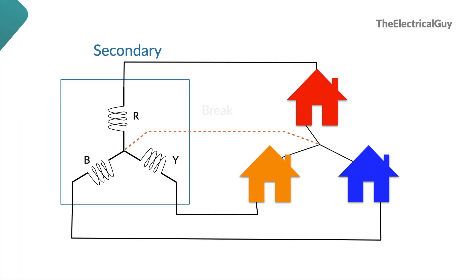Now let's say the neutral wire is broken somewhere. Since the neutral is broken, current will try to find another way to return. This will create unequal voltages across the load. Some loads may have higher voltage than normal and some may have very low voltage than normal. In this case, the phase-to-neutral voltage and phase-to-phase voltage will keep changing as the load varies.